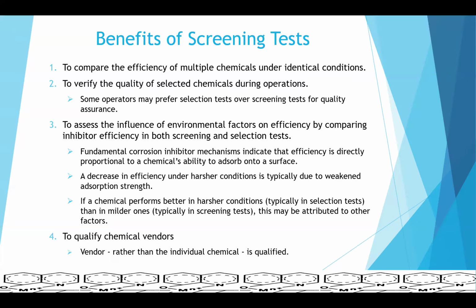Yes, screening tests are short term, but it helps us to compare efficiency of multiple chemicals under identical conditions. This provides a level playing ground to select chemical vendors as well as chemicals. It also helps us to verify the quality of selected chemicals during operations.